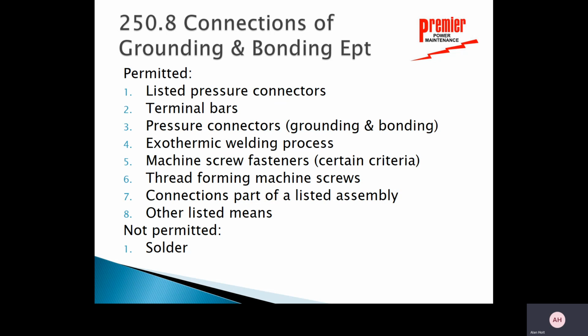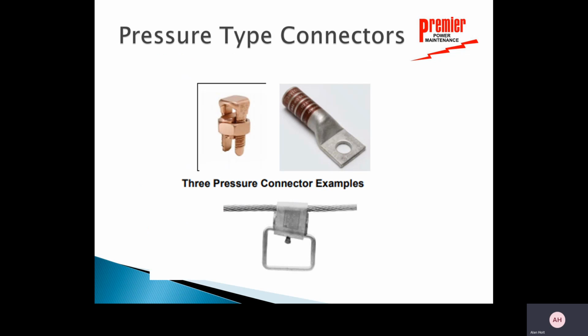There are certain types of connectors that are used. Section 8 of 250 talks about those. There are listed pressure connectors, there are terminal bars, there are grounding and bonding pressure connectors, exothermic welding process, CAD weld, machine screw fasteners with certain criteria to them, thread forming machine screws, like the ones you see in the electrical box that you're putting in your wall for a light fixture. So those are possible methods. Notice that solder is not a possible method for grounding and bonding equipment.